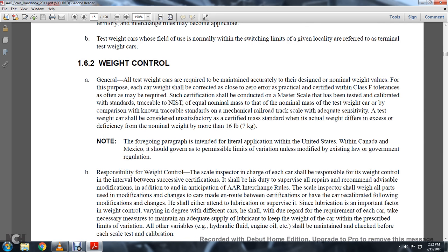Certification shall be conducted on a master scale that has been tested and calibrated with standards traceable to the National Institute of Standards and Technology, equal nominal mass of the test weight car, or by comparison to traceable standards on a mechanical railroad track scale with adequate sensitivity. A test weight car should be considered unsatisfactory as a Certified Mass Standard if its actual weight differs in excess or deficiency of the nominal weight by more than 16 pounds.